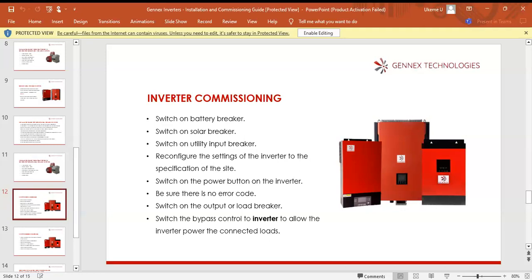Reconfigure the settings. Here we have not switched on the inverter. You have to reconfigure before you power on the inverter. First of all, reconfigure all the configurations, change the ones that you need to change and make sure that it follows the specifications of the components. After doing that, you can now switch on the power button on the inverter. Be sure there is no error code.